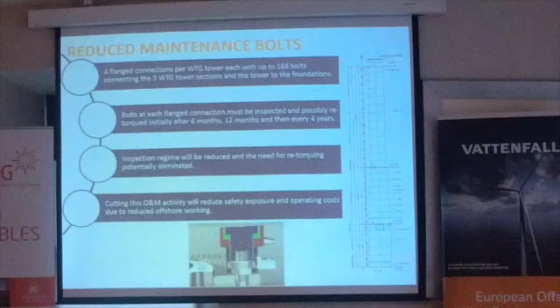So what we're looking to do is implement a reduced maintenance bolt solution. This is achieved by a number of factors, but it's basically better bolt quality, a better bolt design, and very good flange finish tolerances so we get a very good clamp connection. Once we implement this, we hope that after the first initial check, we'll then never have to check the bolts again for the rest of the remaining 20-year design life.